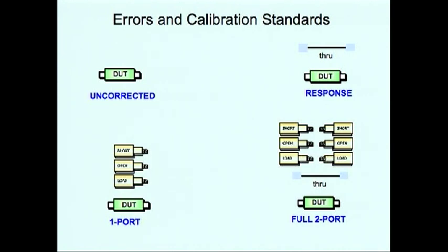The response calibration is easy to perform. It's used when highest accuracy is not required. The calibration removes frequency response errors. The one-port calibration is done for reflection measurements. It requires good termination for high accuracy with two-port devices. The one-port calibration removes errors like directivity, source match and reflection tracking.